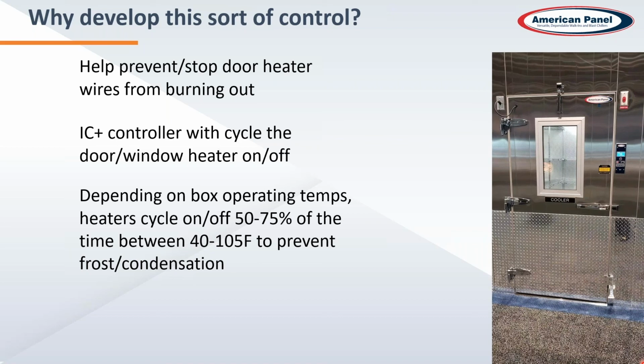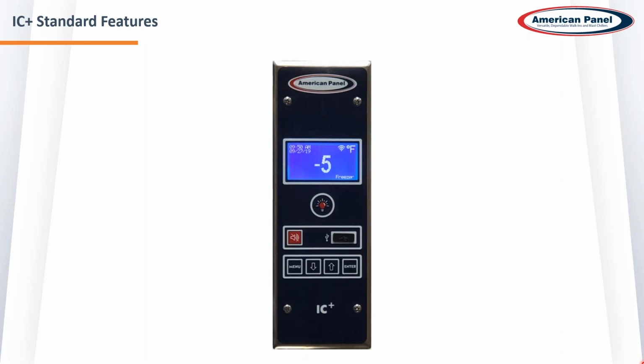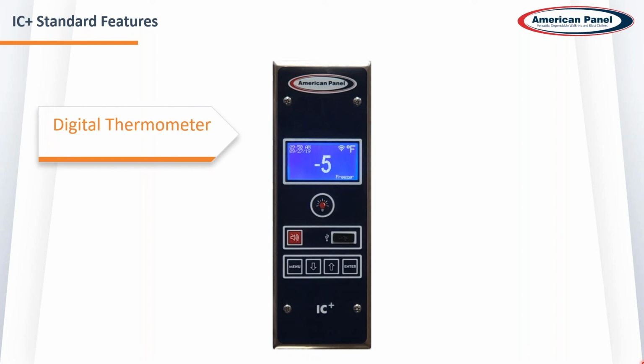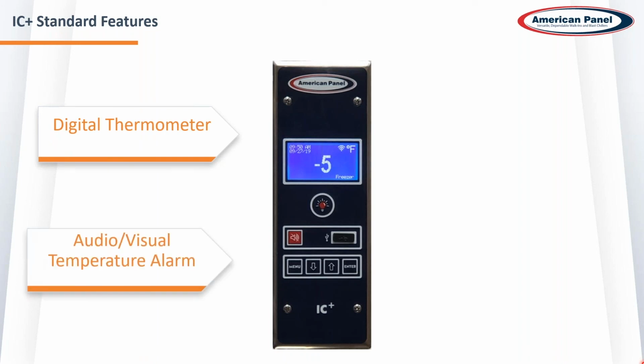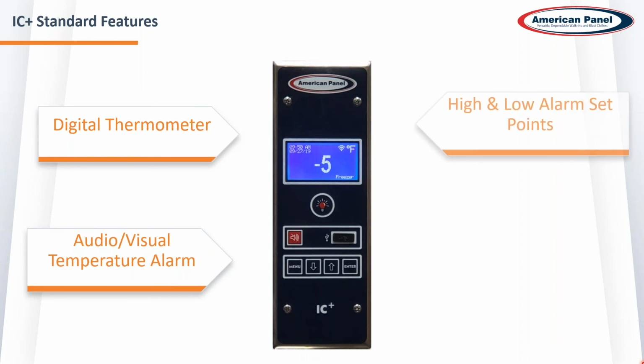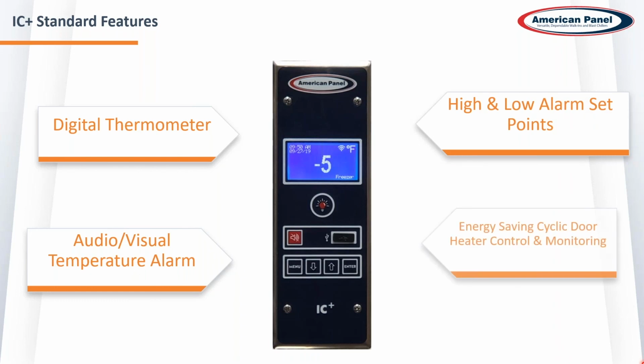Next, let's go through some of the standard features that are included on all IC Plus controllers. First, of course, digital thermometer on our nice bright screen that you can see across the kitchen. Next, like we talked about, the audio visual temperature alarm. You'll get a visual flash of the screen and an audible alarm going off when a unit is out of temperature. The high and low alarm set points, like we talked about earlier, automatically with the intelligence of the controller, it will set those levels. The energy saving cyclic door heater control and monitoring to keep track and save on energy.